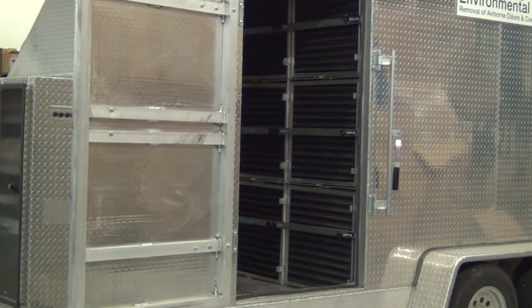So now you can see the HEPA filters are all in place. They're actually being sucked into the frames by the negative air pressure of the blowers. The air is drawn through this chamber, filtered, and then delivered right back into the controlled area.